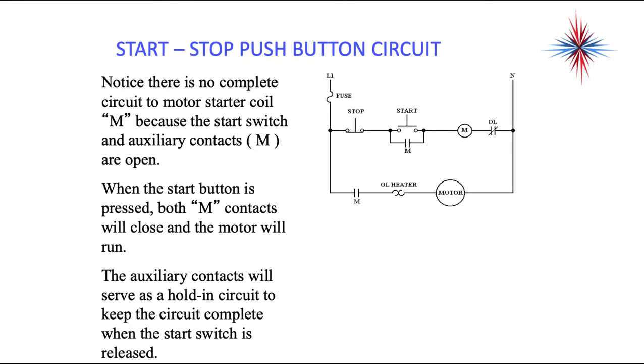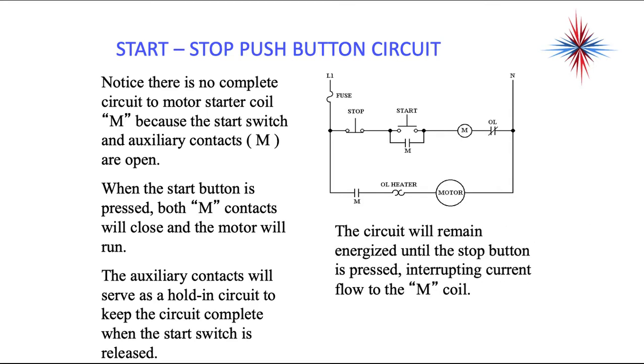If you take a look at this start-stop push-button circuit, we're not worried really about the operation. I'm more worried about the components. Notice there's no complete circuit to the motor starter coil, which is right here. There's no complete circuit because the auxiliary contacts M are open.